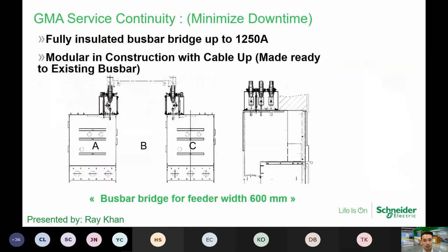All right. So here, this slide talks about the beauty of the switchgear in the modular concept. The modular concept actually enables good service continuity. So this in a way minimizes downtime. All right, so for the panel, you can see in here there's a panel A, panel B, which has been drawn out, and then there's panel C in here. So you can actually shift panel A and C, and you can actually draw out panel B. But after drawing out, what it does is that you can have a bridging busbar in here. All right, so once the bridging busbar is installed, it can power up. Your corporation can actually continue to run itself. So this cable-up concept is actually one of the features from our GIS, which makes the downtime right to the minimum itself. Okay.